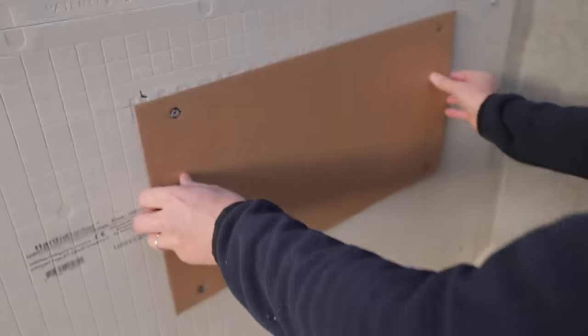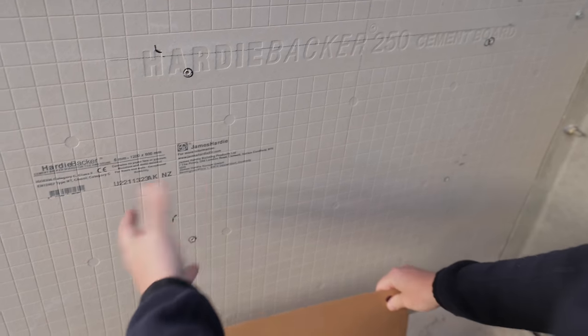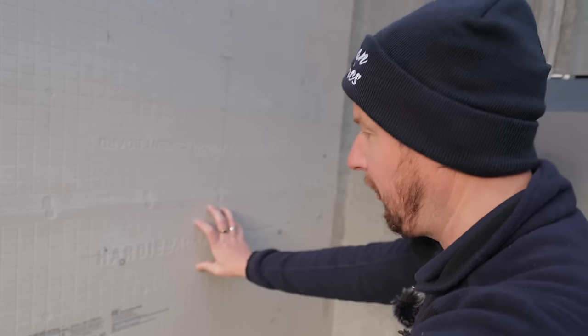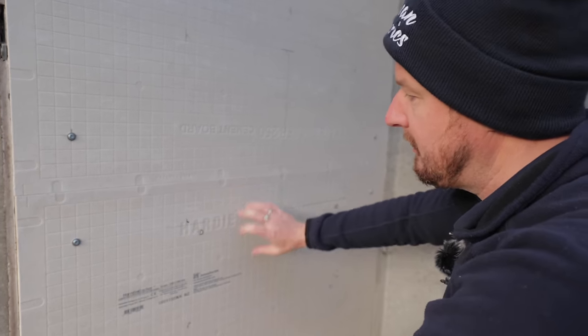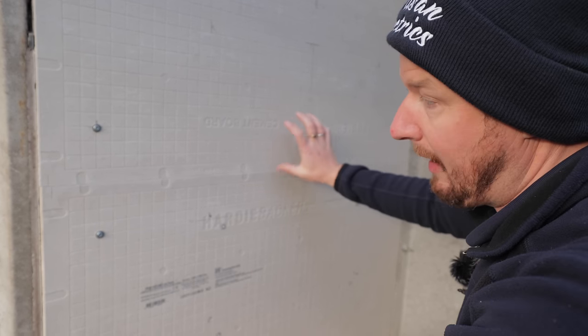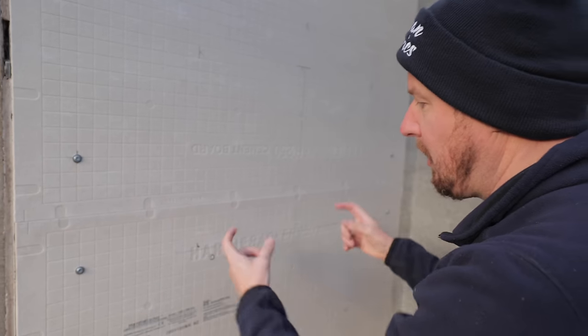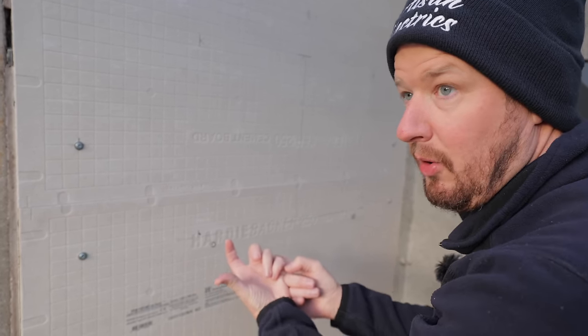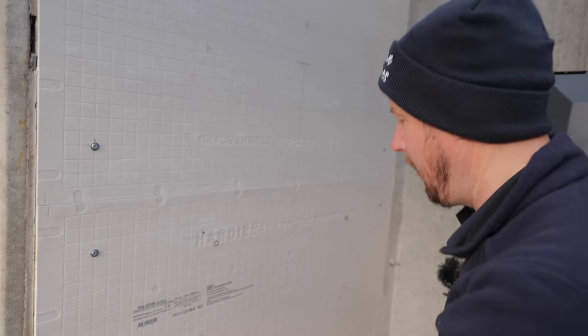We've got this wall template provided by GiveEnergy and we've already pre-marked our fixing holes to make sure it's nice and level. Normally you might mount this on a brick wall, but we like to put HardieBacker on the wall — it's actually a backing board for tiles, but it's flame proof and gives a nice smooth surface. We've put some OSB board behind it because we're in a concrete garage without smooth surfaces, so we've got a solid base to fix to. GiveEnergy provides wall anchors for brick or concrete, but in this case we're going to use wood screws with penny washers.